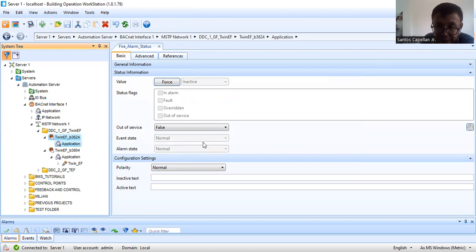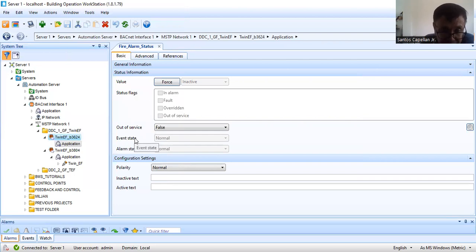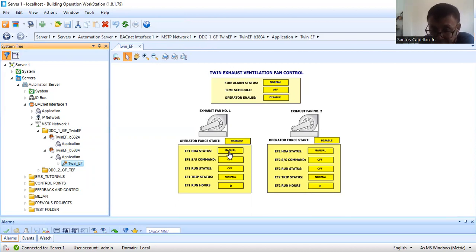Now, if someone turns off the controller or DDC panel and you see some error — like a red cross — all you need to do is recompile or re-download. Go here and download all objects to clear that error. The scope of Part 5 is to show you how to bind the points to the graphics file. As I said, I've created this in advance.